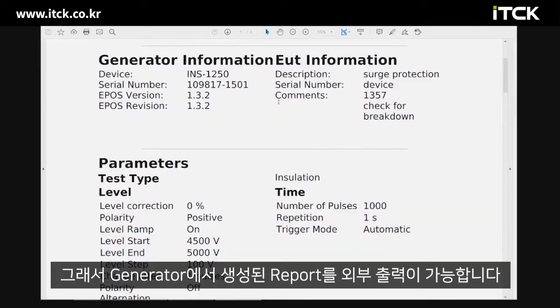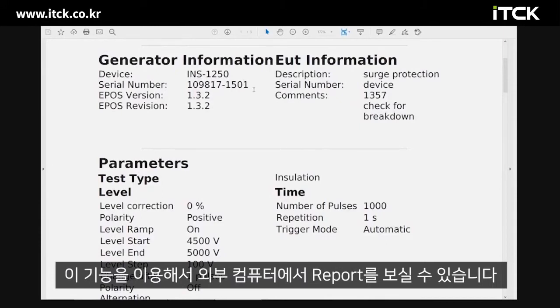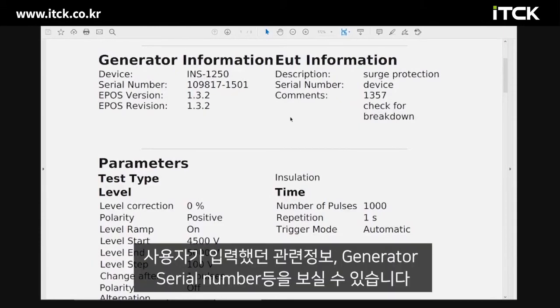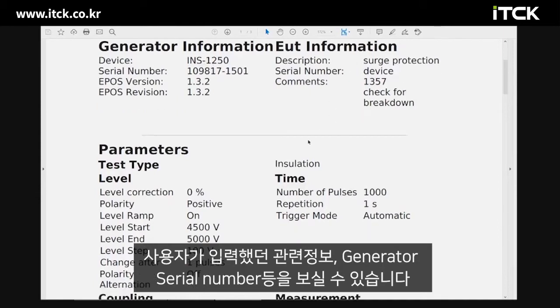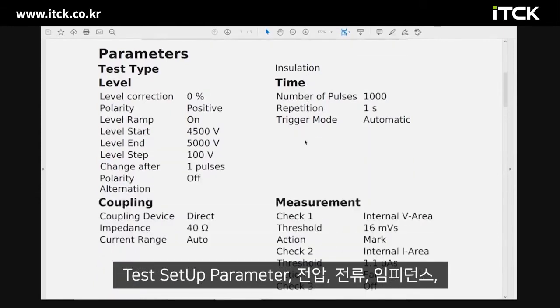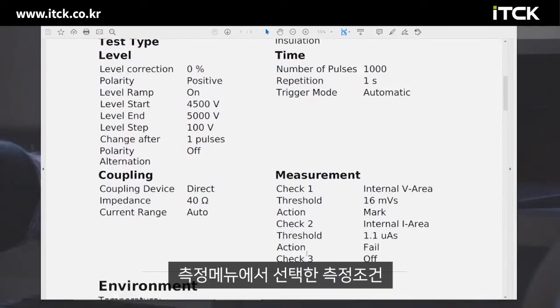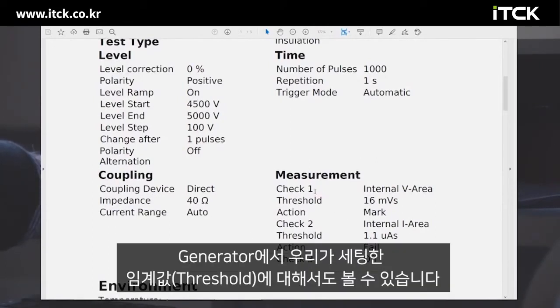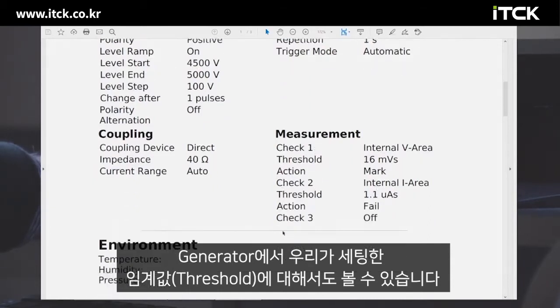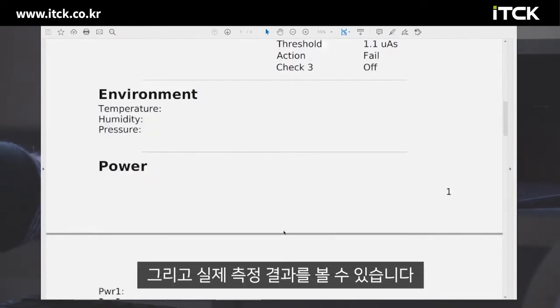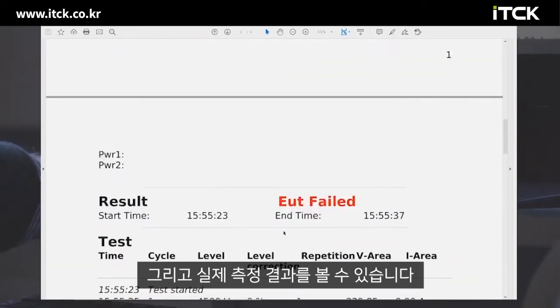So the test report copied from the generator can be viewed on the computer. We see the generator serial number, some information that's been entered by the user, then the test setup parameters, voltage, number of pulses, impedance, then the measurement circuit. Here we spoke about the check thresholds that we can set in the generator, and then we come to the actual measurement results.